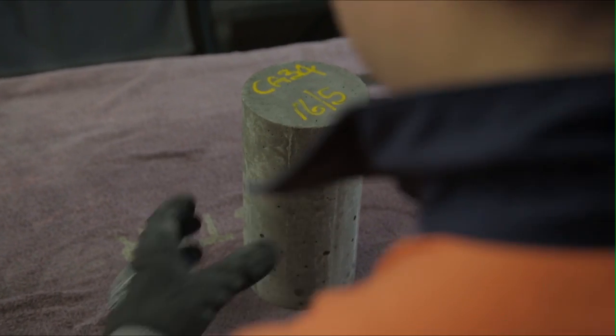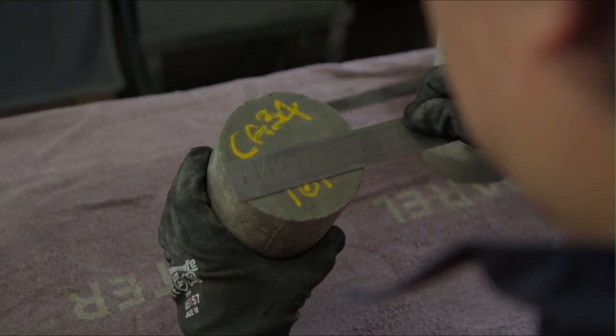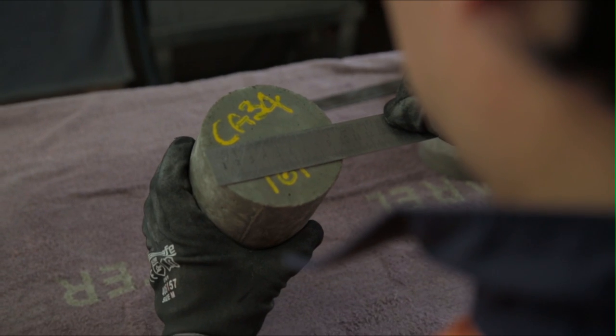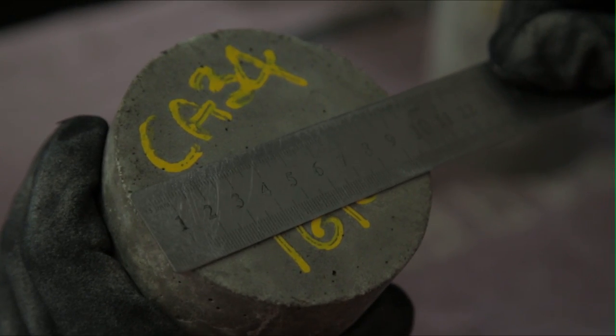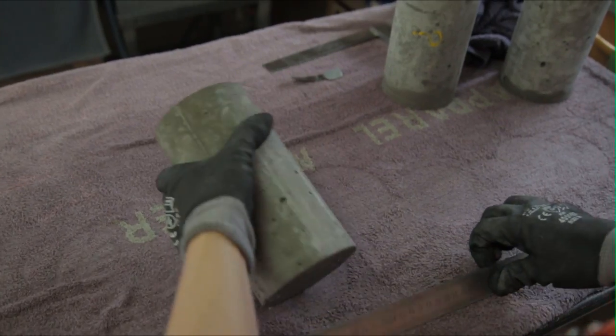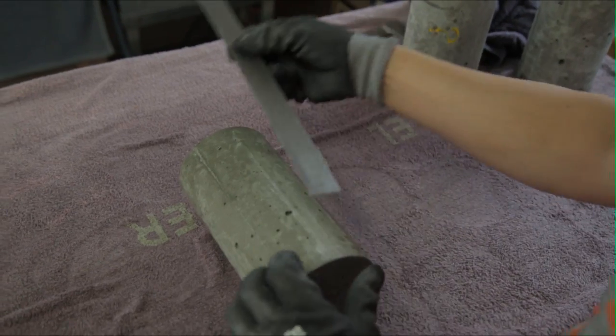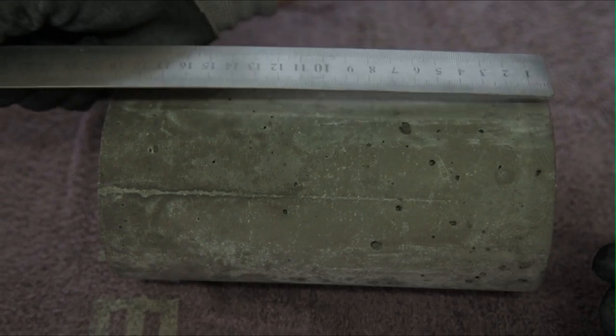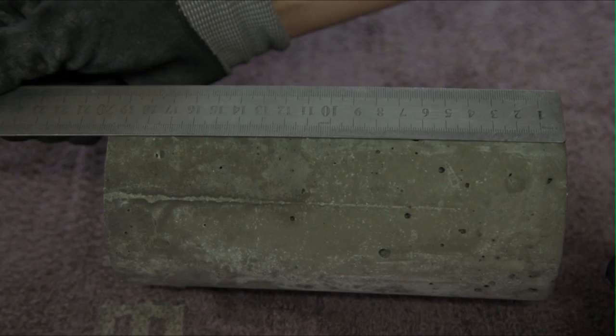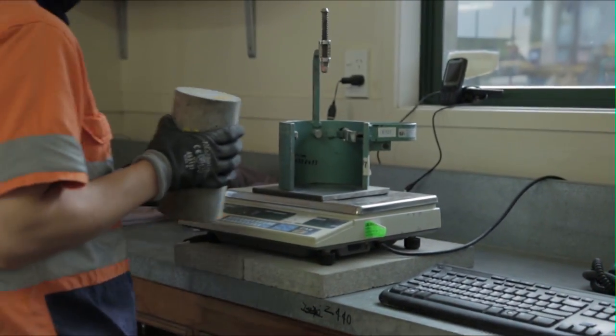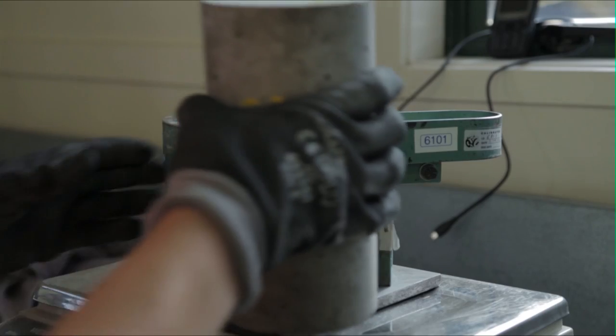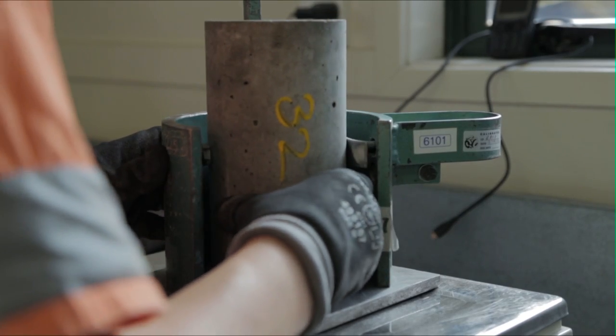The diameter of the cylinder is measured twice near the midpoint to the nearest 0.1 millimeters, with each measurement approximately at right angles to the other. The two measurements must be within 2% of each other. The height of the cylinder is also measured to the nearest 0.5 millimeters. The ratio of the height to the diameter must be between 1.9 and 2.1.